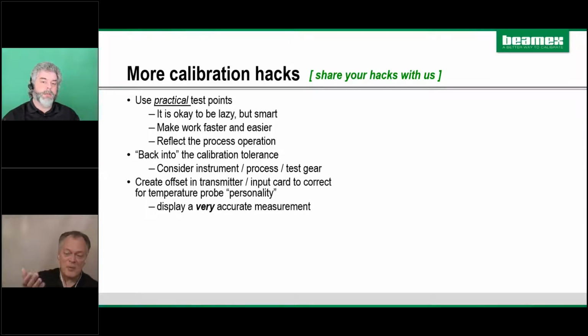And as an example, anybody out there that's maintaining a flow computer, like pipeline people, that's exactly what they do. They just make adjustments in the computer. They do not touch the transmitter. They don't worry about the probe unless there's a problem with the probe. If the probe needs to be replaced, they replace it, but then make an adjustment in the computer. It's really simple, and it helps you make a very accurate measurement. Yep, and it's thinking outside the box. Exactly. So use this concept if somebody's pushing you for better accuracy in the control room.